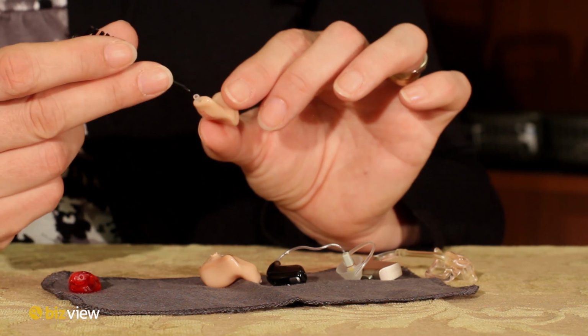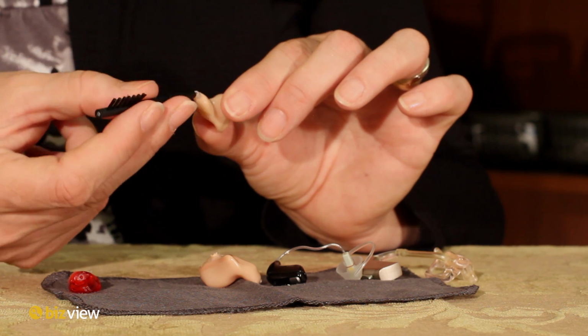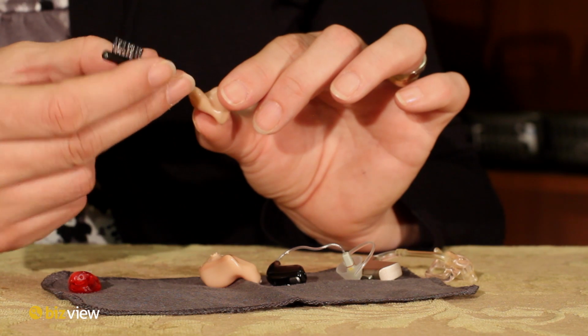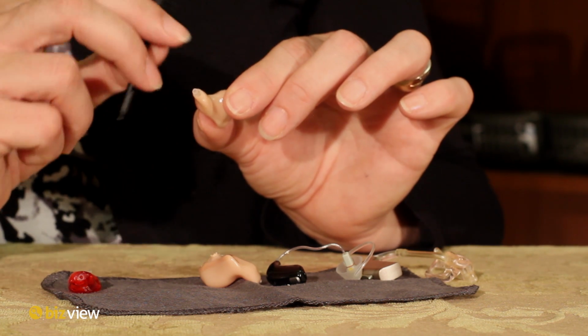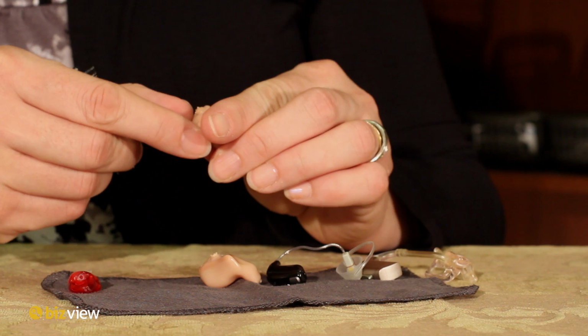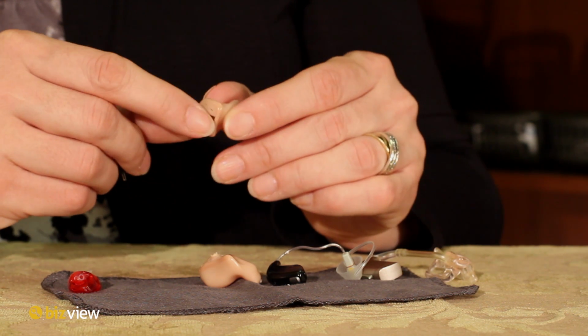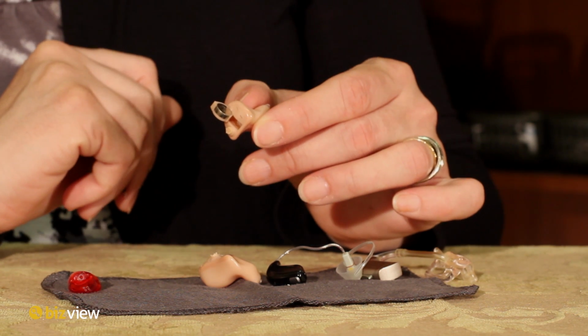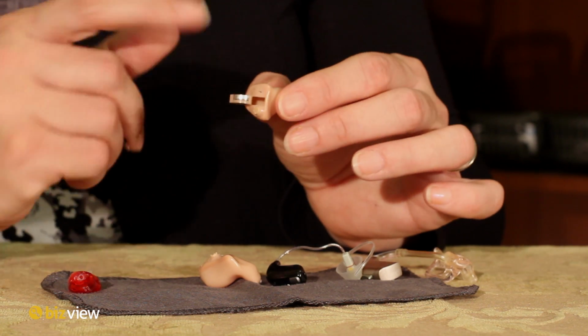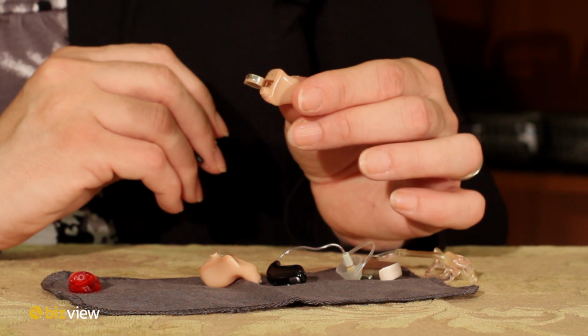With the in-the-canal type hearing aid, basically you want to make sure that you always clean the receiver tube where the sound comes out of, and you would do that by using the wire loop on your cleaning tool. And you just insert it inside the tube and flick it to make sure that there's no debris inside it. You want to open the battery door. So when you open the battery door, just open it all the way and make sure that it stays open. That way it stops the battery from draining.